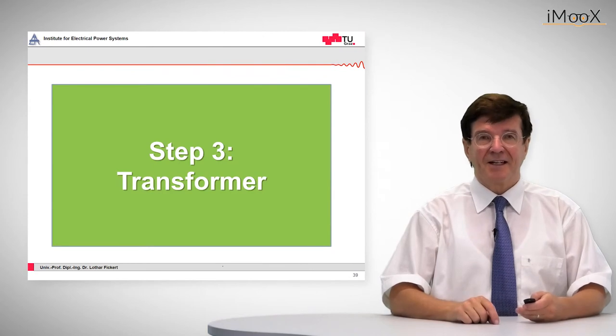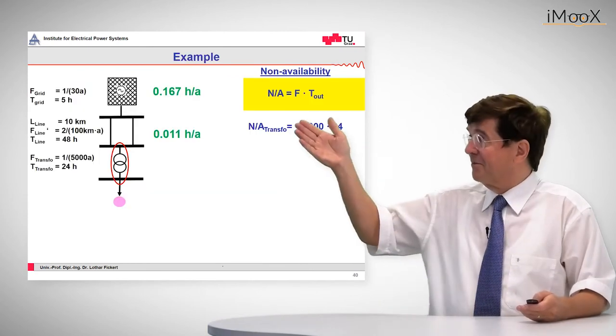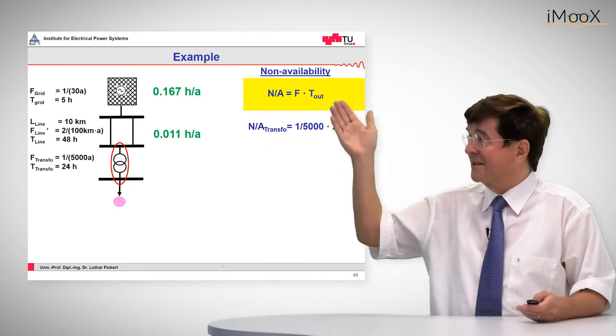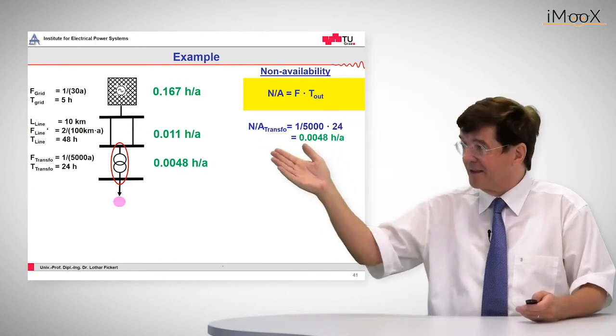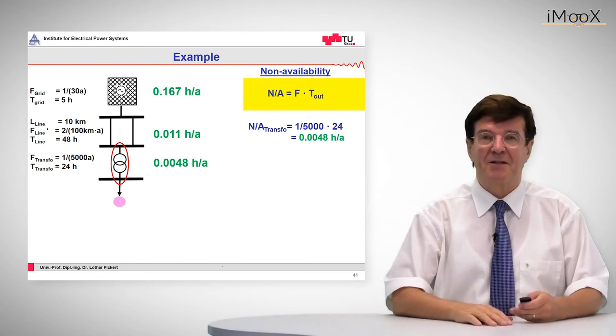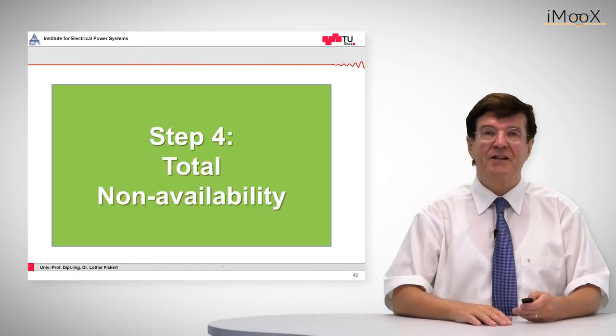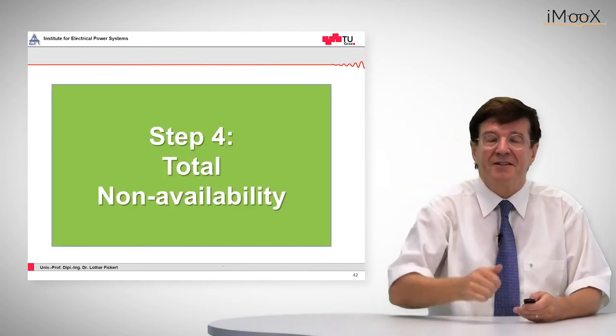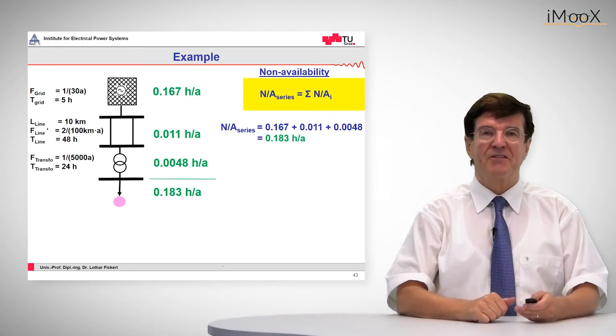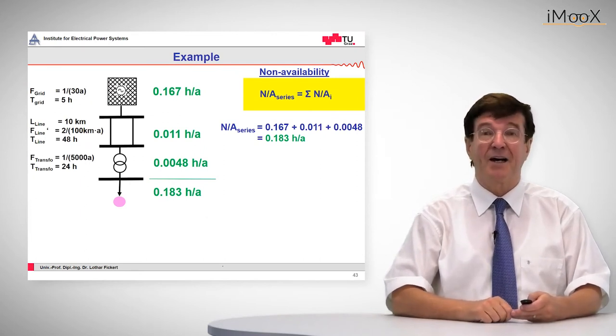Element number 3 is the transformer, obtained by frequency times average outage time. This has a non-availability of 0.0048 hours per year. The total non-availability of these serial elements is the sum, which comes out as 0.183 hours per year.